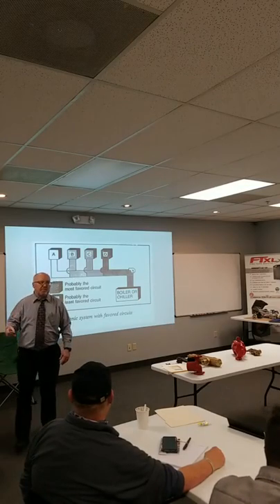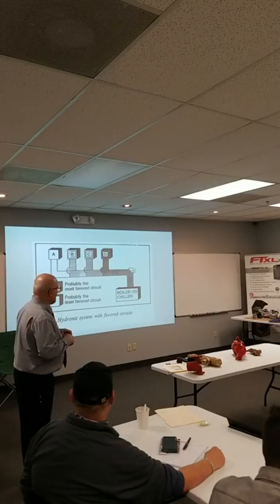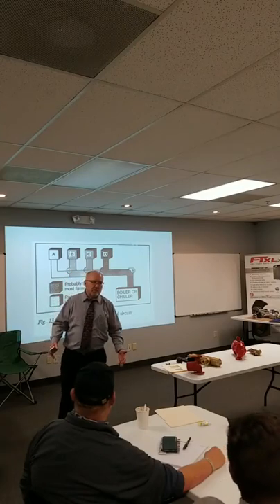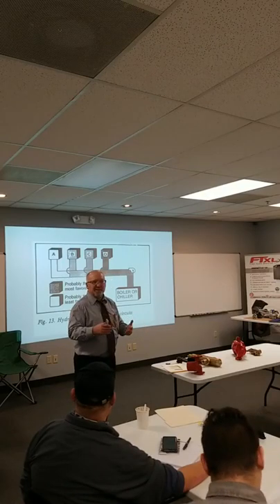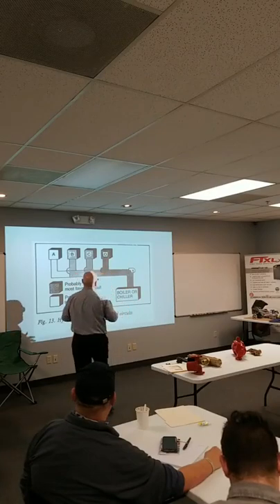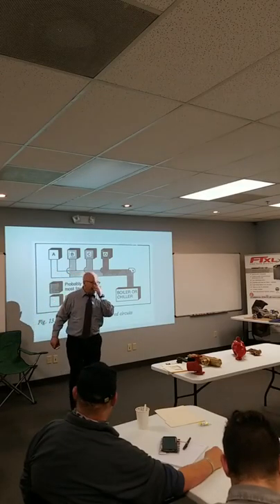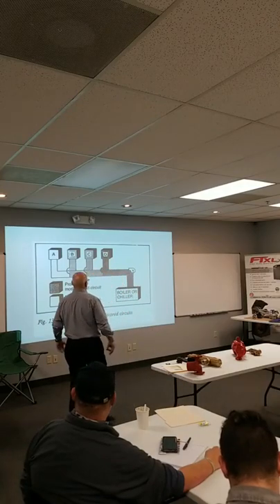Balancing, 9 times out of 10. I love selling bigger pumps, guys, commercially, but there's so many times when we go out there and they say, you know, this is the third pump I've been to, and I still can't get heat at the end. 9 times out of 10, it's a balancing issue, because I'm telling you, the original pump, it's kind of like boilers. A lot of them are 50 to 100% oversized. That's why your discharge valve is throttled. Tell me that it's been running fine for 40 years. Yeah, sure. But he calls me every year and says I don't have heat at the end. And I say, well, let's balance. Nah, we need a bigger pump. Okay, I'll sell you a bigger pump, but let's balance also.